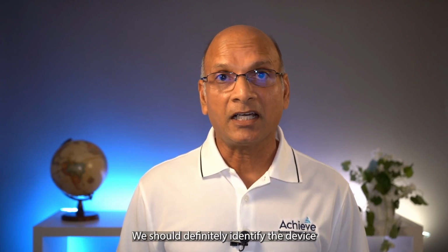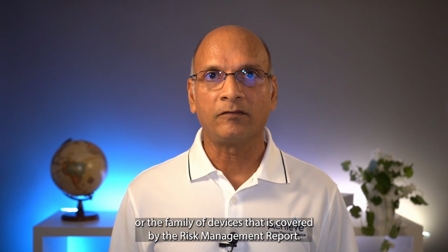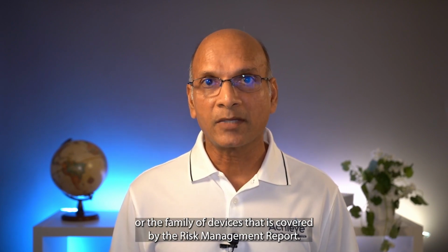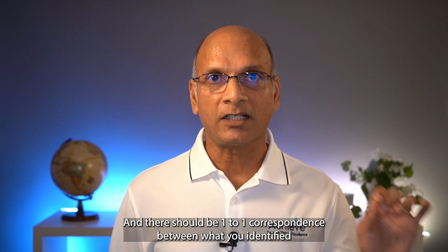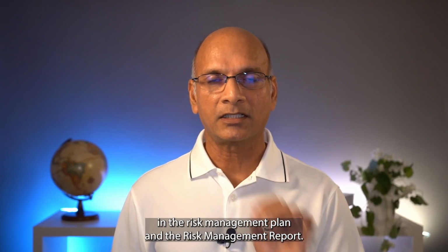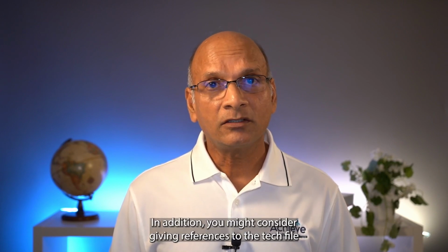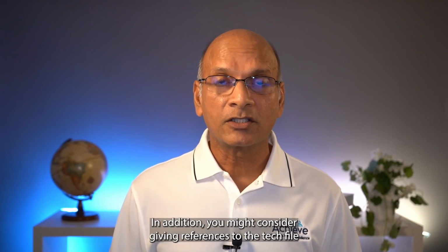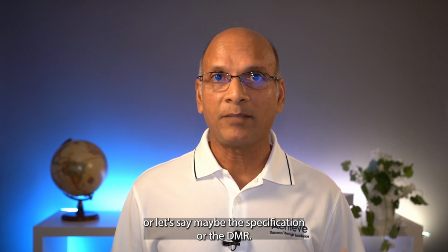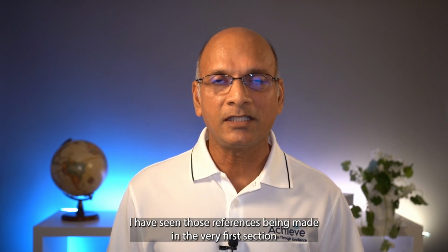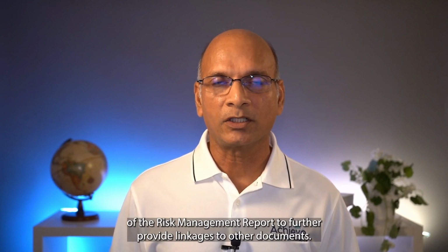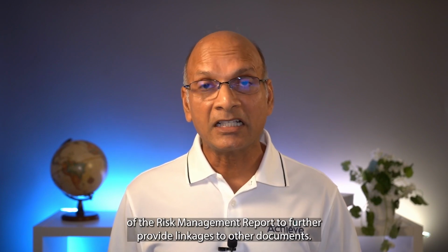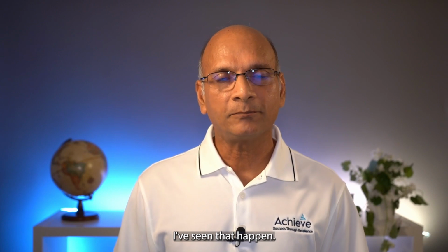We should definitely identify the device or the family of devices that is covered by the risk management report, and there should be one-to-one correspondence between what you identified in the risk management plan and the risk management report. In addition, you might consider giving references to the tech file, or maybe the specification or the DMR. I have seen those references being made in the very first section of the risk management report to further provide linkages to other documents. I've seen that happen.